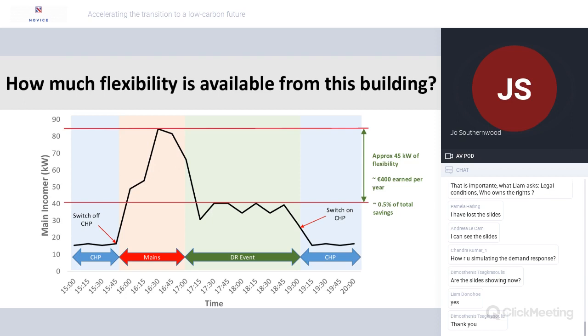But to measure what the flexibility potential is, we had to first switch everything over to mains. So what we did was we ramped down the CHP until we turned it off at around 4:30 in the afternoon. That's the peak you can see in the red period of the graph. You can see that if the site didn't have a CHP, it would normally consume around 85 kilowatts at that particular time.